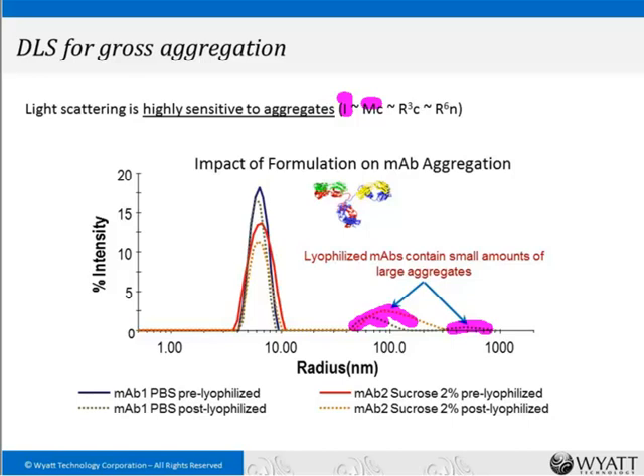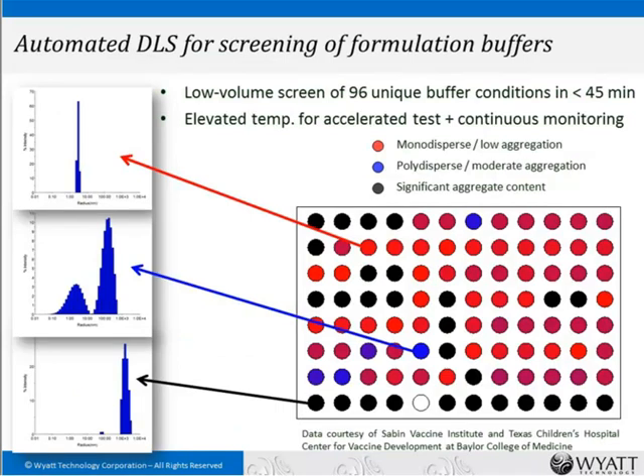The DYNAMICS software running the plate reader can be set up for a thermal map. Here, red wells are color-coded to indicate nice monodisperse solutions — about five nanometers, basically a monomeric protein. Blue wells indicate moderate degrees of aggregation, and black wells are 'black holes' where you have micron-sized, precipitating aggregates. This takes less than an hour to run, and you get a nice visual map giving a quick indication of which formulations are worth proceeding with.